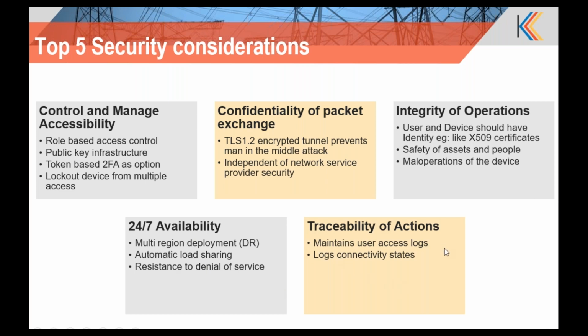Traceability of operations or actions invoked by the user is also important. For example, if a user sets particular settings on the inverters, all operations performed on these devices should be logged and available for future audit trail purposes, mainly for tracking and ownership of each action taken by individual users. These logs should be available in standard repositories, such as a syslog server or third-party syslog services.